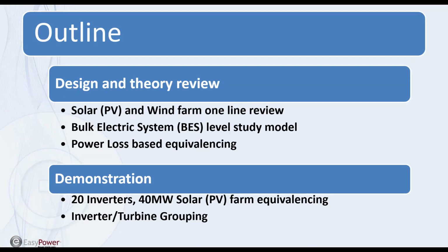So after that, we will switch from the presentation to a live demonstration, using a 20-inverter, 40 megawatt solar farm as an example, and we will demonstrate how we equivalize this one-line to a BES study level model. After that, we will introduce some topics about inverter turbine grouping. As you can see, if we have 20 inverters in a 40 megawatt solar farm, each inverter would generate 2 megawatts, so we have the same size of inverters throughout the plant.